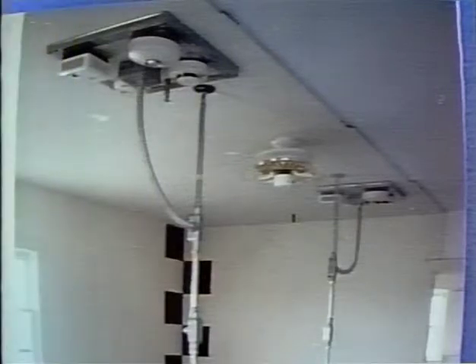The fire detector devices to be tested were mounted on prefabricated panels. These panels were installed at 2 locations at the ceiling of the living room, equal distance from the point of origin, at the center of the bedroom hallway, and near the center of the kitchen ceiling. The intensity of the heat and smoke generated in many of the fire scenarios would be great enough to cause the various detectors to alarm and, in most cases, render the detectors unusable for subsequent test. Additional panels were fabricated to replace the used detector panels. A system of threaded metal bolts embedded in the ceiling joist was devised to permit easy exchange of the panels when necessary.